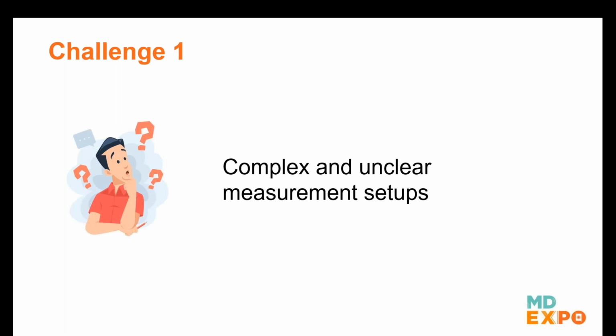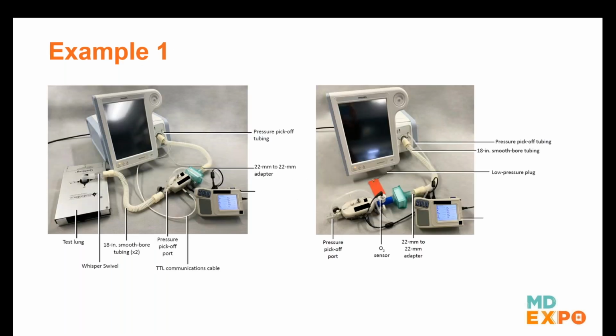All right, first one. Let's talk about setups. You may or may not recognize these, but here's a couple of photos in my first example. This is directly from a service manual. It's 2 photos of 2 different setups using a flow analyzer to do testing on a ventilator. They did actually a pretty good job here because they took photos. They show you a bunch of connections. They show you the tubing connections, the cable connections. They show you the ventilator. They show you the analyzer, and they show you a test lung if there is one.